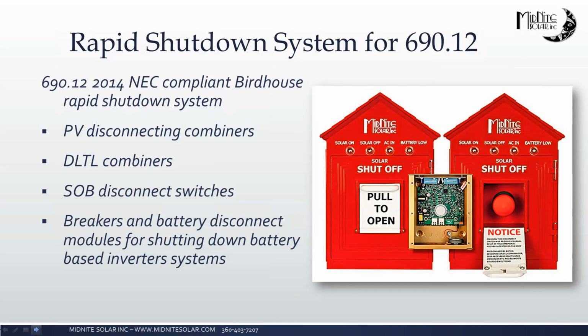The birdhouse is battery powered. It has AC backup for redundancy, and it also charges its batteries from the PV during the day. We do recommend a 120 volt dedicated branch circuit to the birdhouse just so the batteries stay topped off, especially if you're in New England and you get a lot of snow and it might be a week before the PV gets sun again. Just nice to have that in there. The AC is the last thing that it's used, but it will keep the batteries topped off.